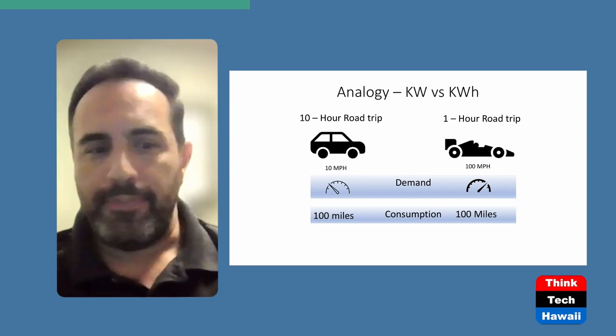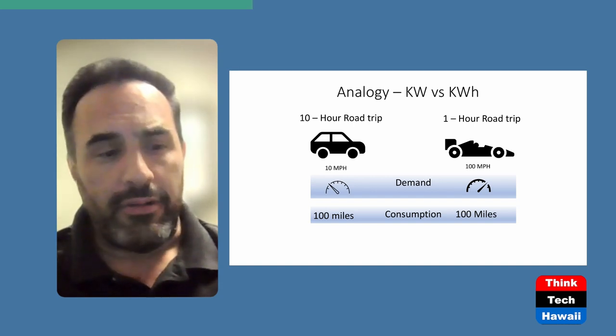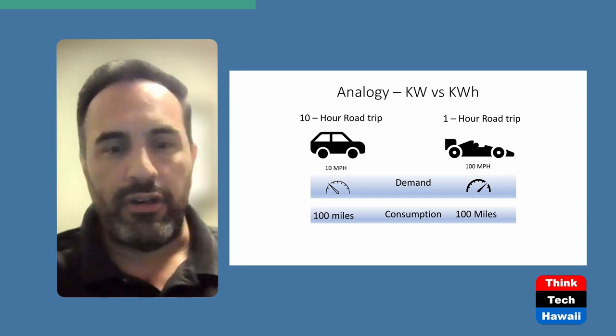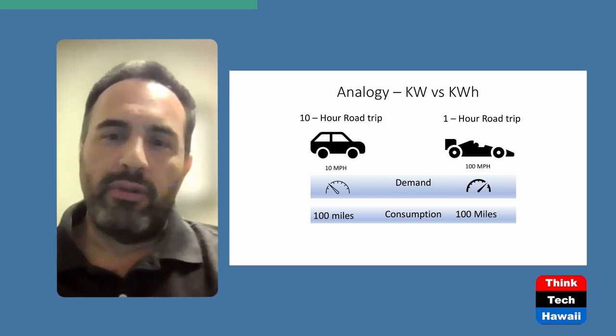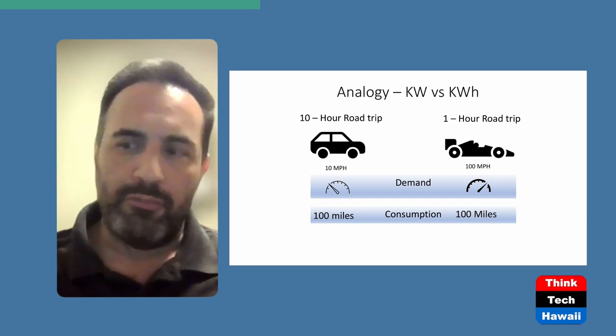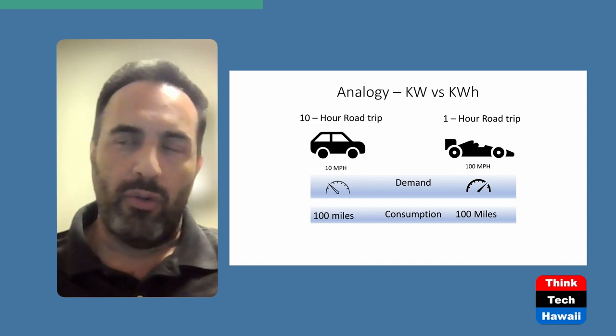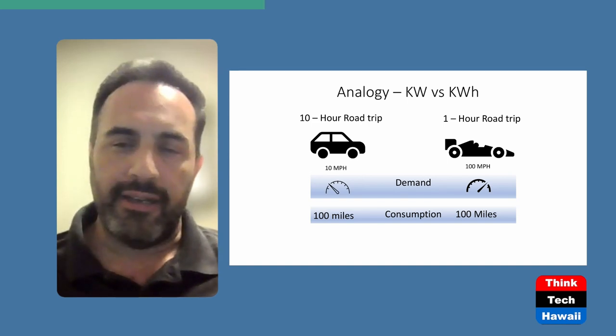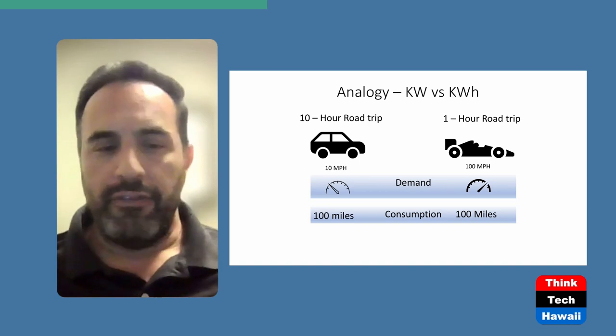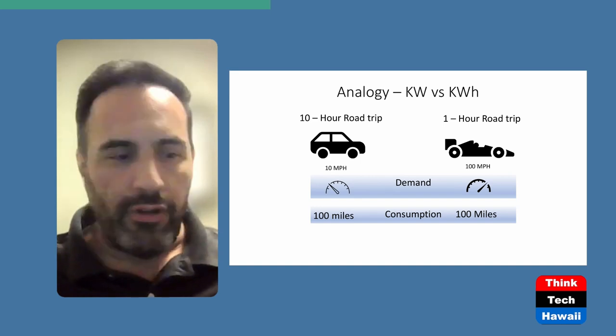That's the difference I'm trying to point out. Describing a resource purely in kilowatt hours or megawatt hours doesn't accurately explain its instantaneous capability. When we discuss or promote renewable resources — or any resource — describing production in energy units makes sense for billing, but it is misleading when you want to understand how much you can support at any given time. The instantaneous demand, in megawatts, is what matters. If your peak load is 20,000 megawatts and you only have 18,000 megawatts available, you are deficient 2,000 megawatts and will have to shed load.